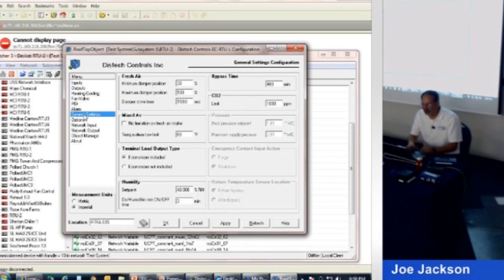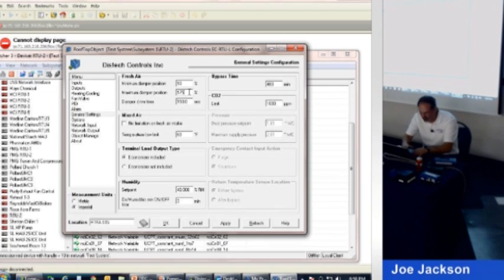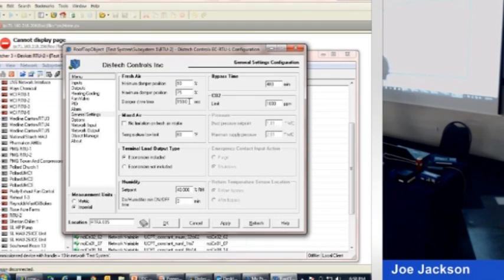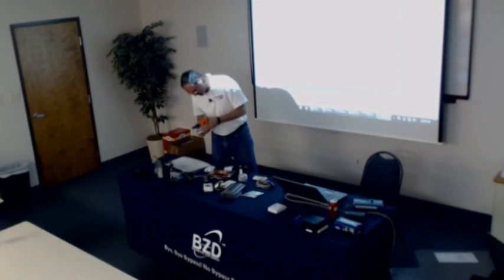Some general settings. Here's for your fresh air. Let's say you want 10% minimum fresh air. And I don't know why you wouldn't want it to go to 100%, but let's say there was a reason you never wanted the damper to go over 75% of the way open. Oops. You could limit how far it goes open. Dampers, most damper actuators are 0 to 10 volts. But they also make them in what we call floating point, which means you power to drive one way, you power to drive the other, and it knows where it is based on time. And so, like this valve here is not floating, but if it was floating, it has a drive time of probably 90 seconds, but I don't see it written on there.